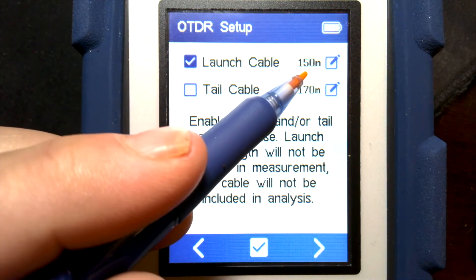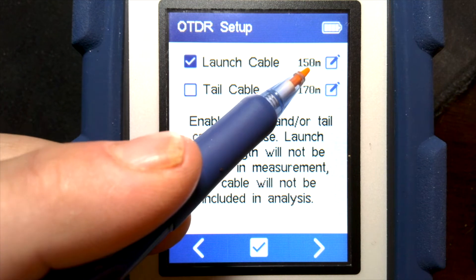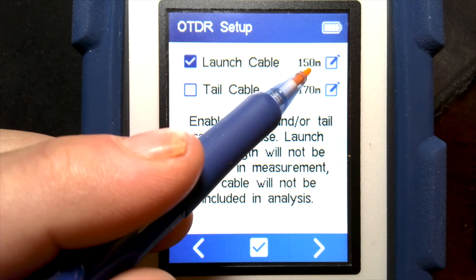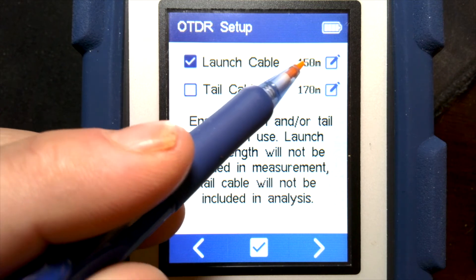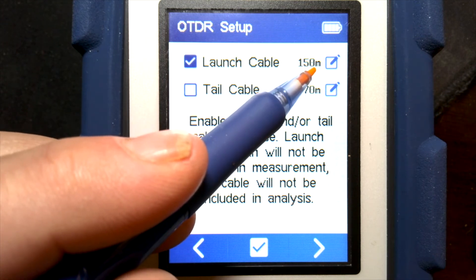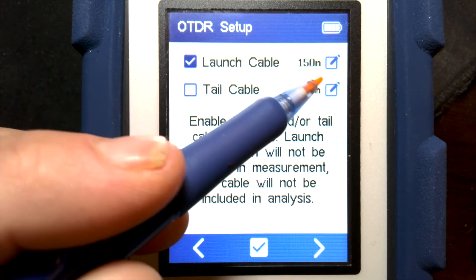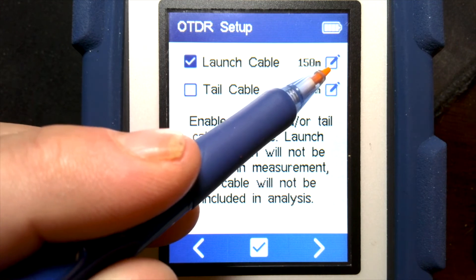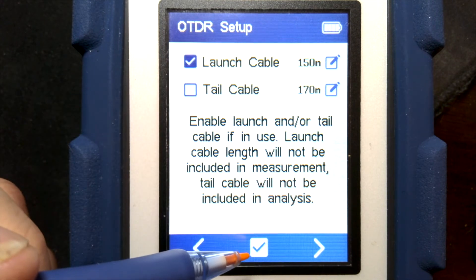I have the launch cable set to 150 meters, but we saw that the first event is actually at 160 meters, so the launch cable is 160 meters long. There's a plus or minus 10% scan range — so whatever you enter, it looks at plus or minus 10%. Entering 150 meters gives a window of 135 to 165 meters. As long as the launch cable is within that window, it will detect it. I could type in 160 meters and it would then look at 160 plus or minus 10%, but in this case it will pick it up since we're inside that 10% window.